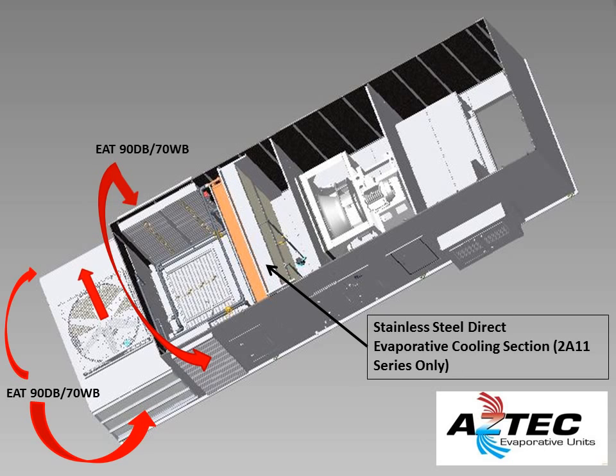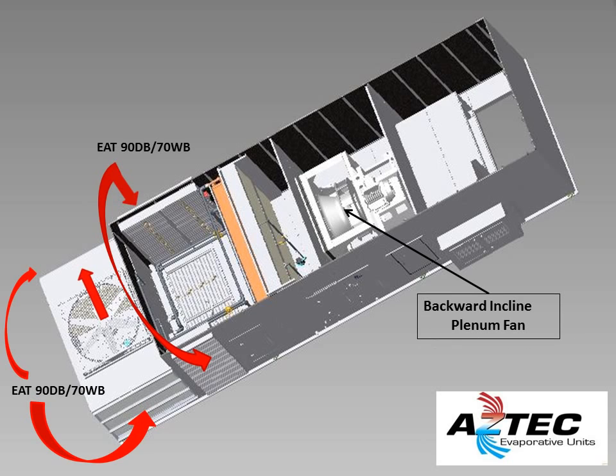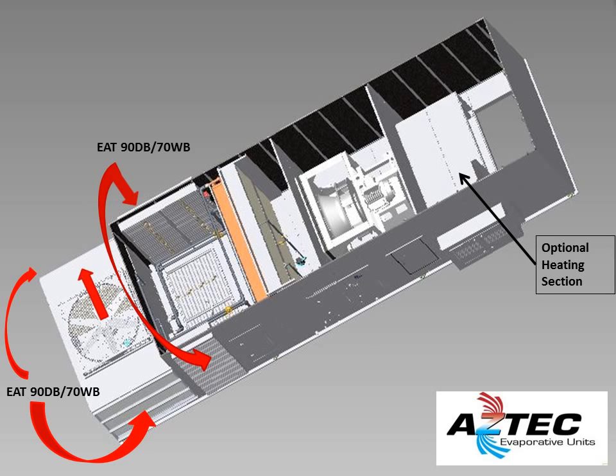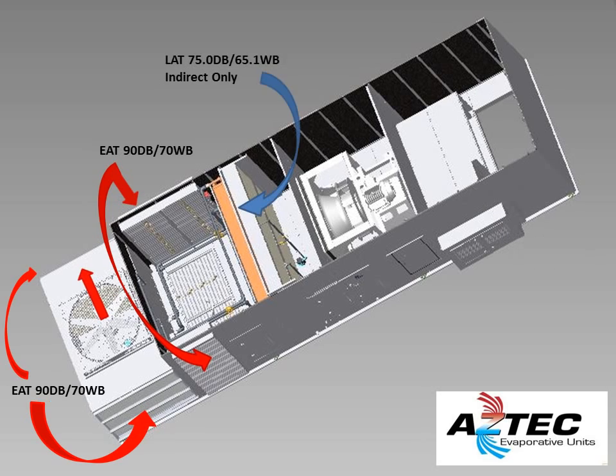Next in line is our stainless steel direct evaporative cooling section. Consider this the second stage in this two-stage hybrid. The first stage lowers the dry bulb and wet bulb, and the second stage further lowers the dry bulb using the first stage results as a starting point. Here you see the backward inclined plenum fan, which can handle high static pressure, is more efficient and quieter. We also have an option for heat with this unit: either gas, electric, steam, or hot water.